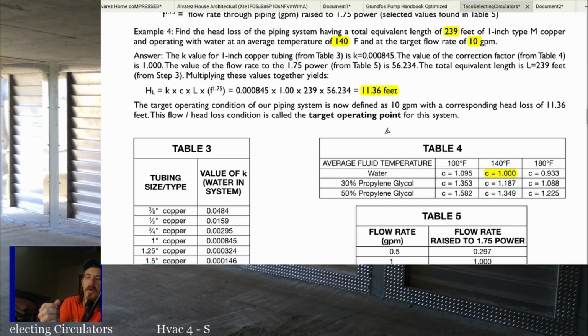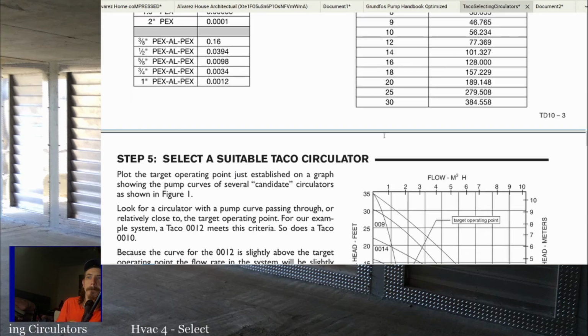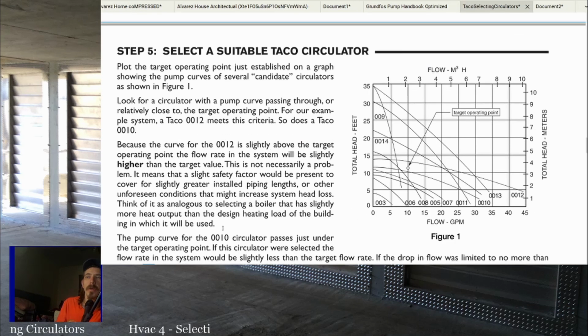So now we know how many GPM we need and how many feet of head we have to work against. So the target operating condition of the piping system is 10 GPM at 11.36 feet of head. The head loss is the target operating point for the system. All right. So now you just got to select a circulator.